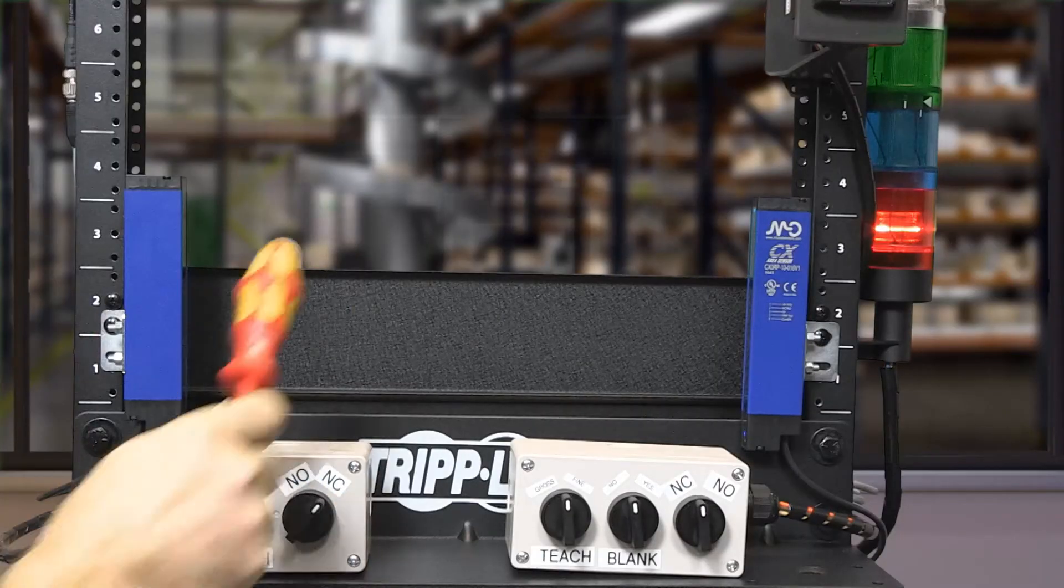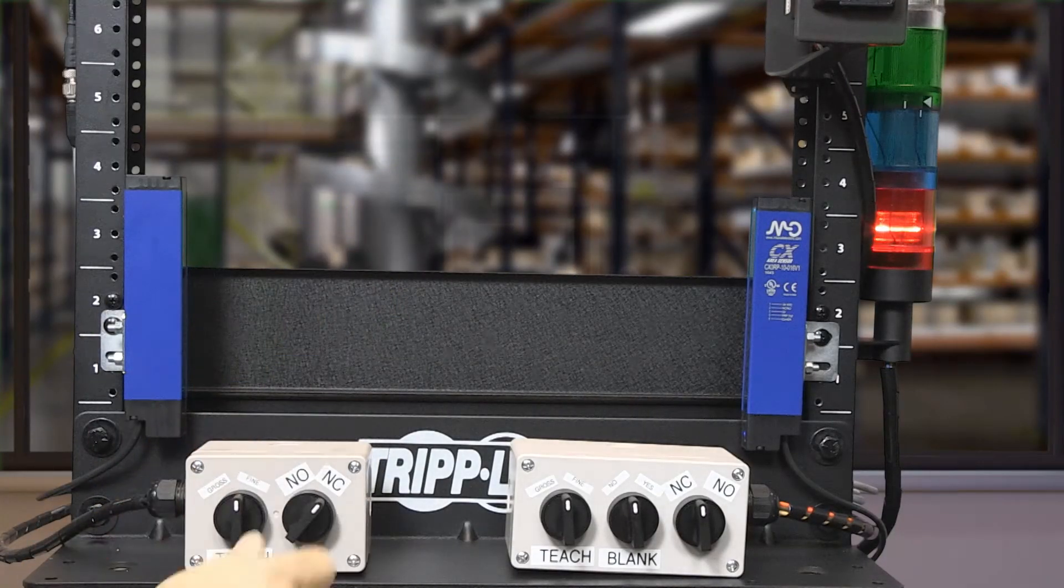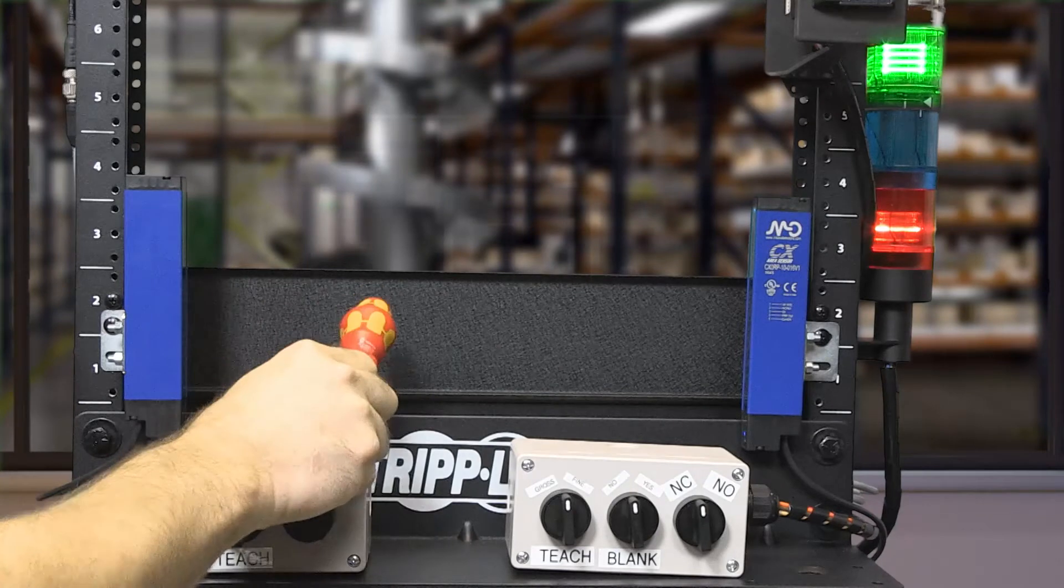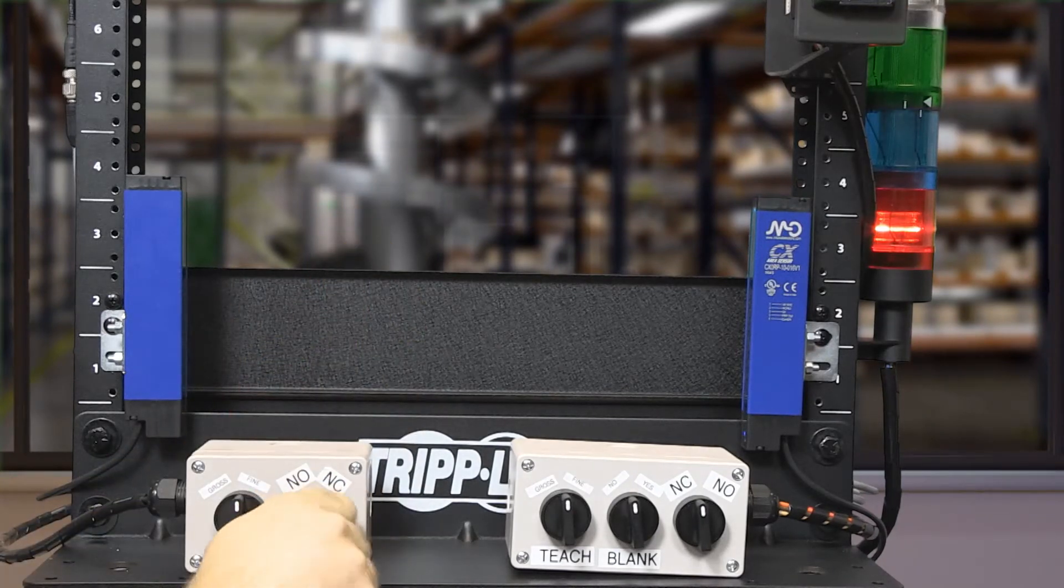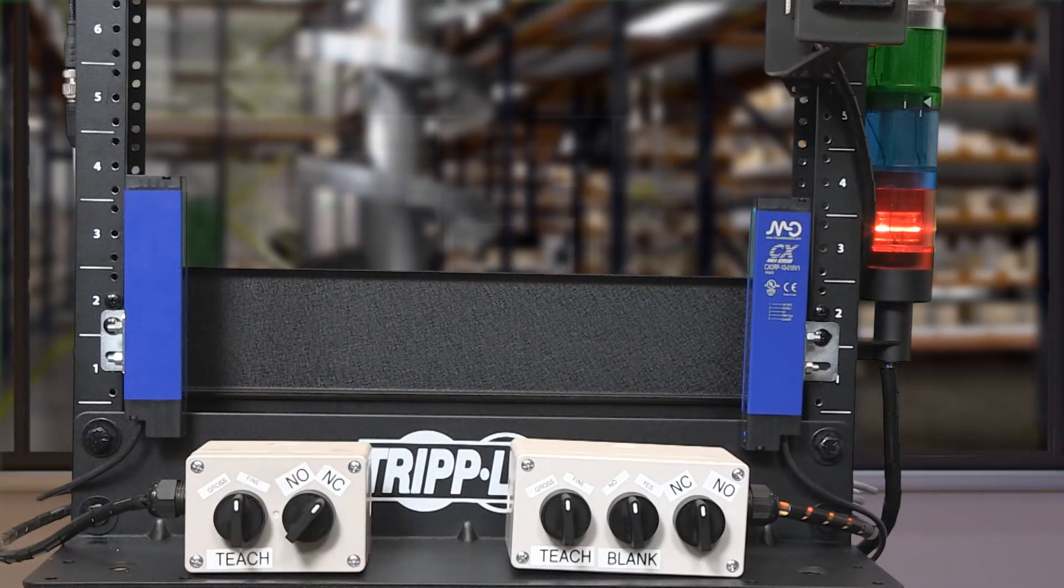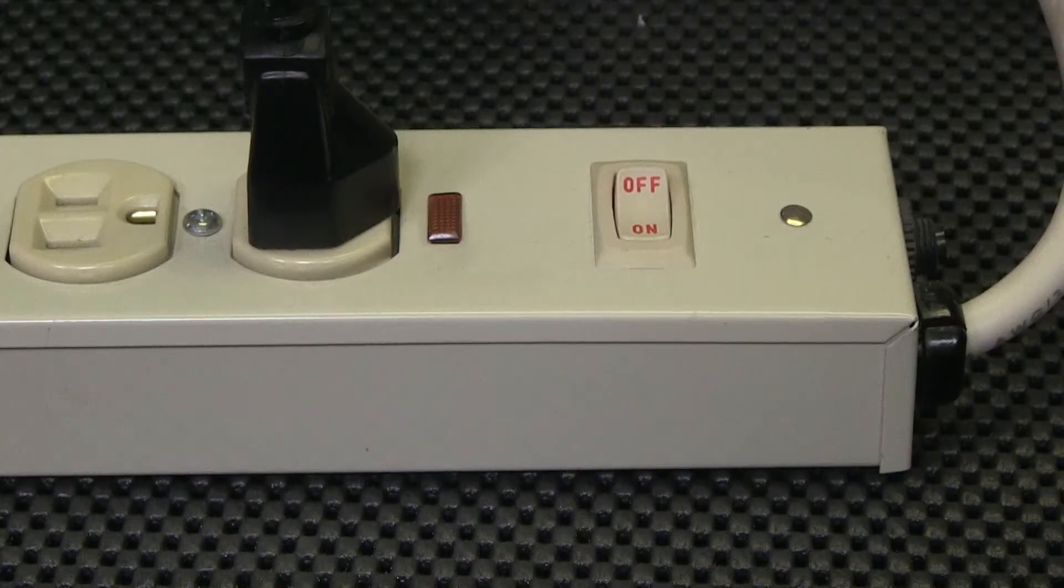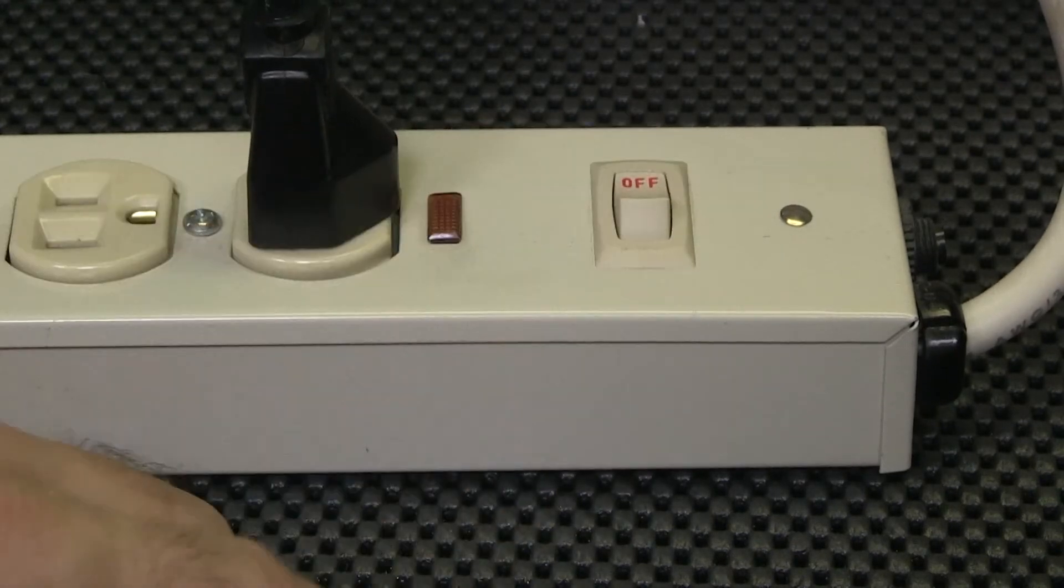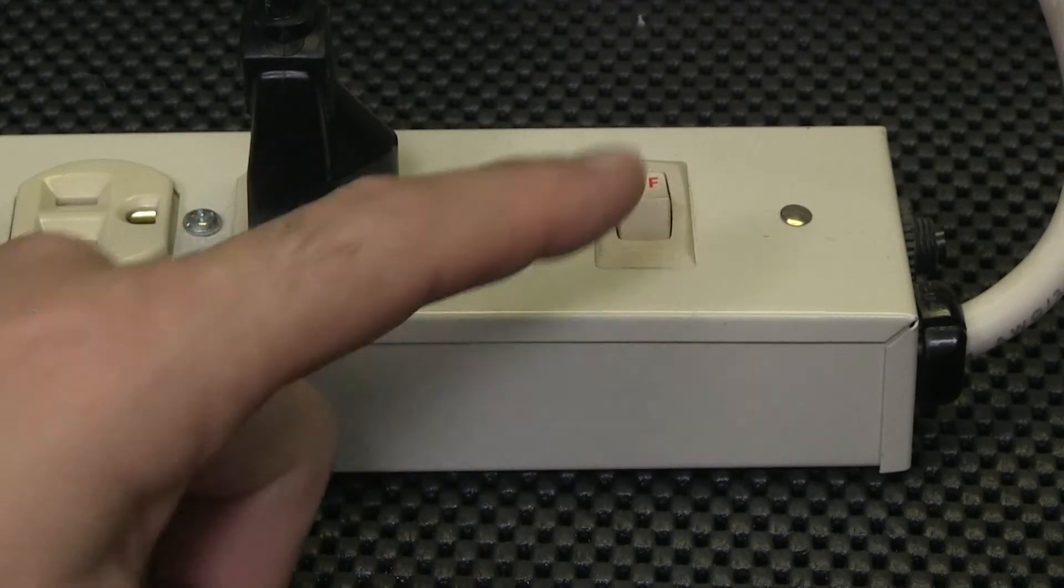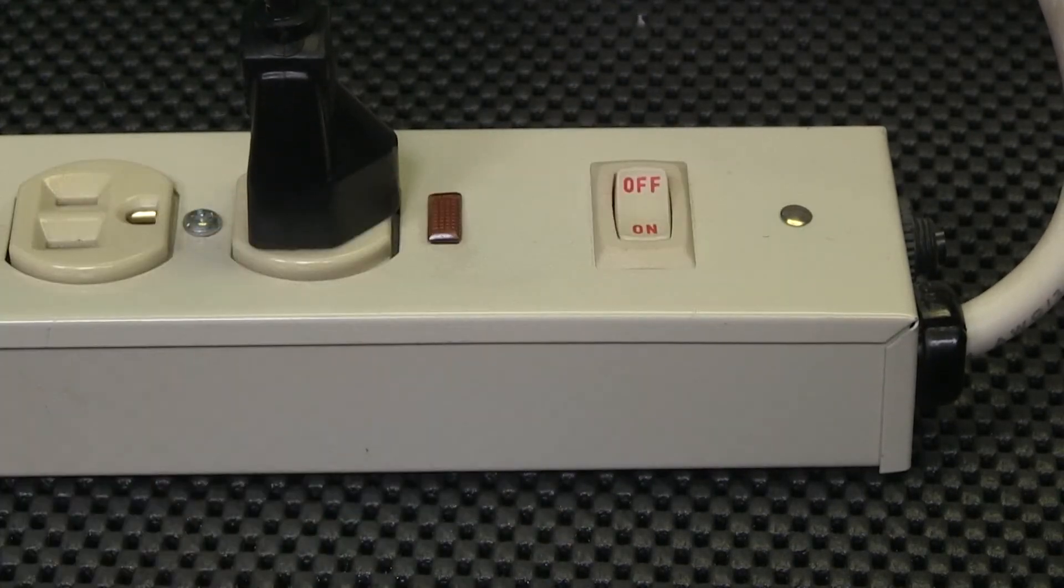Making changes to the normally open, normally closed only takes place on power up. If I attempt to change the setup after the sensor is powered up, nothing will change. I must power down, select normally closed, and repower the system.